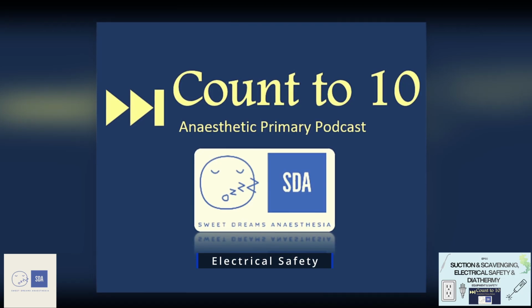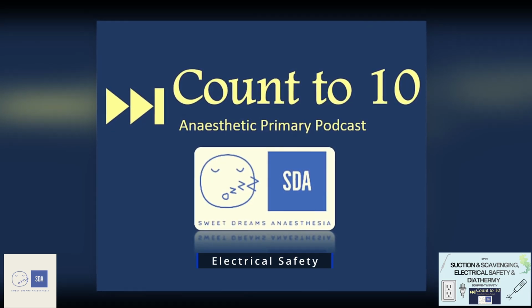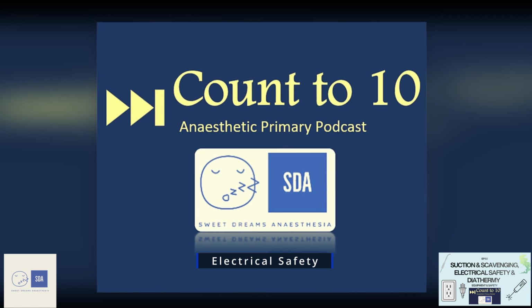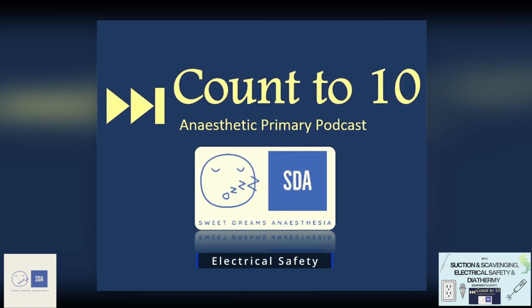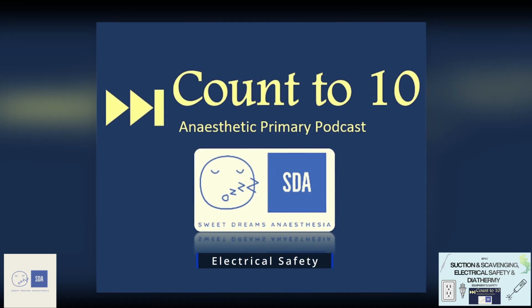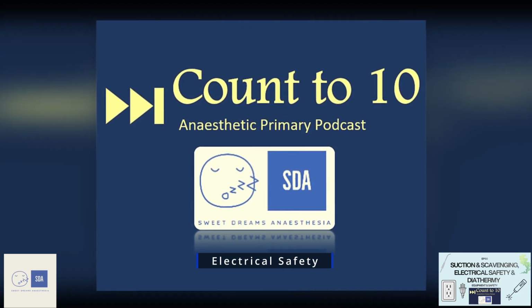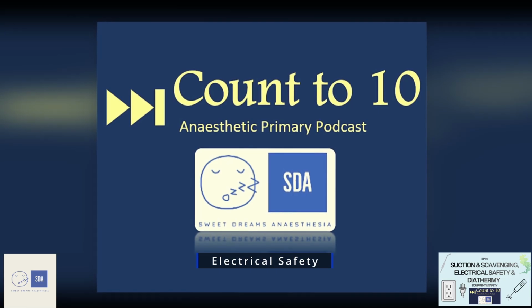You can easily identify RCDs within the operating theatre because on the power socket it should say RCD protected, and typically the RCDs are linked to the red power points, and therefore they're usually linked to a secondary power supply, so they're not part of the UPS system.